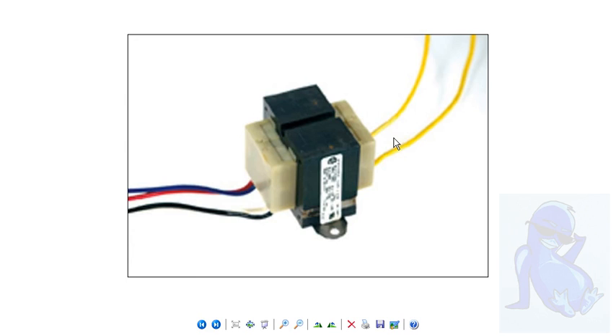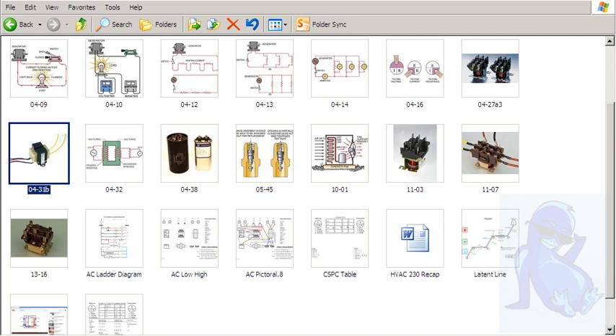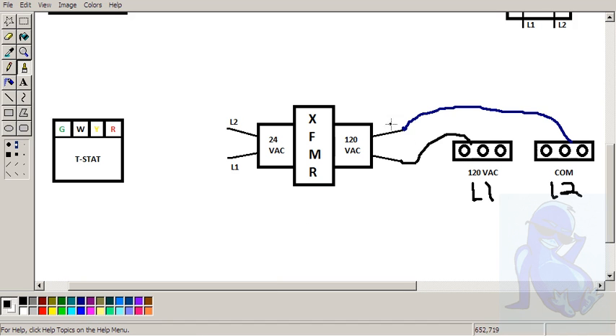And then on the other side it's going to come out lower voltage. So you're going to hook up your two lines, your common line, your 120 volts. It's going to come out here after it goes through the windings, and it's going to be stepped down to 24 volts. So my red is going to be my power again. And we're going to let that 24 volt power go into my thermostat on the red line. It's labeled red. That's my power going into the thermostat. The thermostat is a switch.